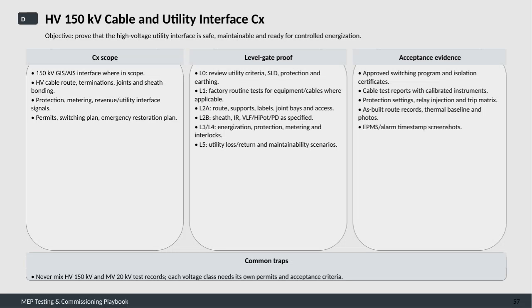This slide focuses on the testing and commissioning process for the high-voltage 150 kV cable and utility interface. The main objective here is to ensure that the high-voltage utility interface is completely safe, maintainable, and ready for controlled energization.